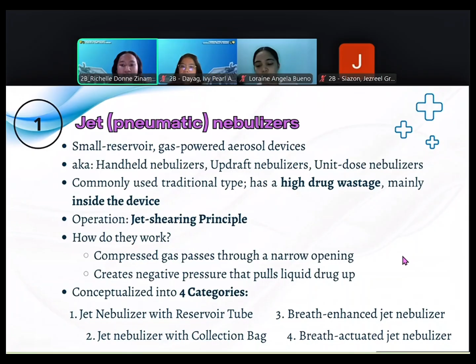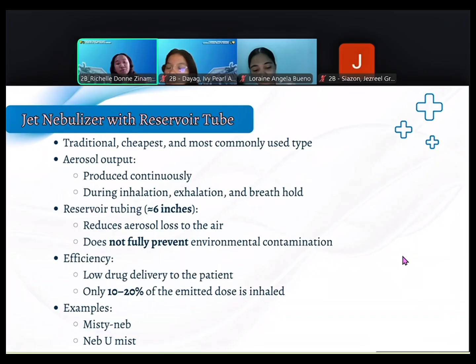Its aerosol output is produced continuously, during inhalation, exhalation, and breath hold. Its reservoir tubing has a size of 6 inches, which is convenient because it reduces aerosol loss to the air, though it does not fully prevent environmental contamination. For efficiency, it delivers low drug delivery to the patient, and only 10 to 20% of the emitted dose is inhaled. Examples of this are Misty Neb and Nebu Mist. Next slide.